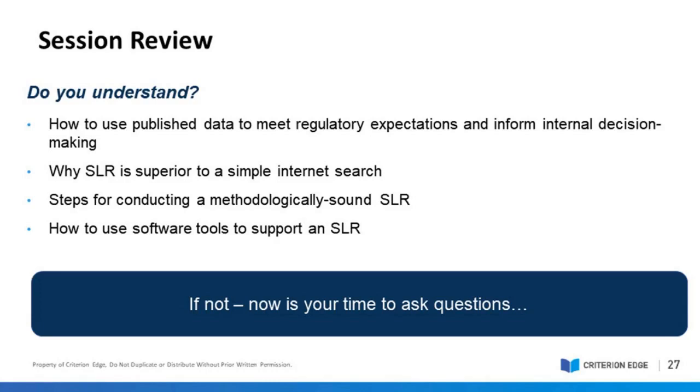That's a great question, and it takes me to one of our favorite topics at Criterion Edge, which is the development of the state-of-the-art section of the CER. The state-of-the-art goes to the heart of this particular question. This question is about where I can find guidances to describe the state-of-the-art of the therapeutic landscape in which my device exists. The job of the state-of-the-art section of the CER is to establish the current technology of which your device is likely to be included. And does that technology align with current best practices, current professional guidelines, and are the outcomes of safety and performance consistent with what's being seen in the literature?